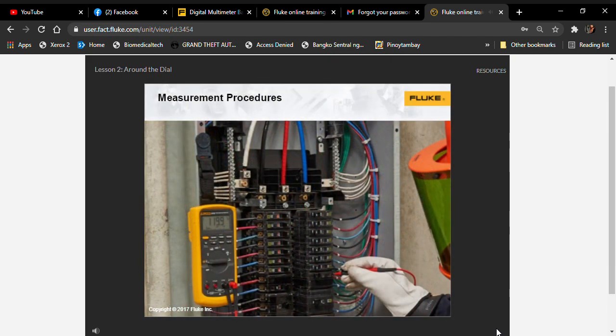It can prove difficult to both hold a multimeter and test leads safely when taking a measurement. Instead, look for a safe location to place the multimeter so your hands are free to hold and concentrate on the leads. Often, it's best to use a magnetic hanger for the meter. This is attached to the back of the multimeter so that it can be temporarily placed on the side of an enclosure or on nearby equipment. Be sure to keep the display visible.